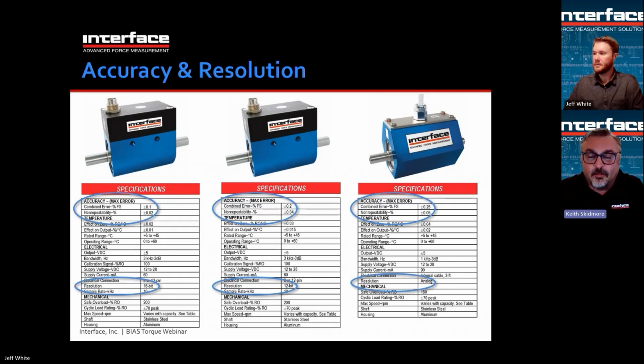Many of them are 24-bit. Most times the 24 bits are not usable, so you might have 17 or 18-bit max out of a 24-bit system. 12-bit is less resolution, obviously. And then to the far right, sometimes it's not a bit. If there's not an analog to digital or digital to analog converter, there is no bit resolution. So the sensor on the right uses a frequency converter, and that's typically considered an analog device, and so the resolution is considered analog.